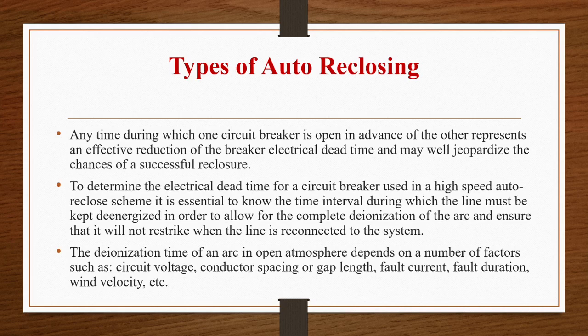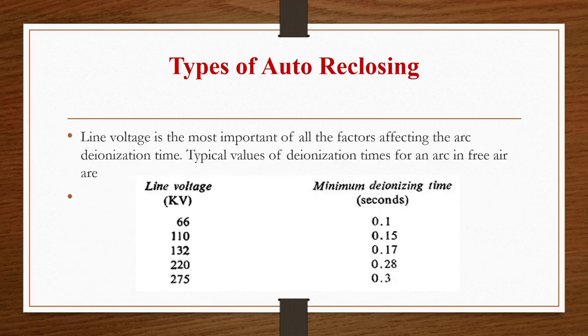To determine the electrical dead time for a circuit breaker used in a high-speed auto reclose system, it is very essential to know the time interval during which the line must be kept de-energized in order to allow for the complete deionization of the arc and ensure that it will not restrike when the line is reconnected to the system. So the deionization time of an arc in open atmosphere depends on a number of factors such as circuit voltage, conductor spacing or gap length, fault current, fault duration, wind velocity, etc. Line voltage is the most important of all the factors affecting the arc deionization time.